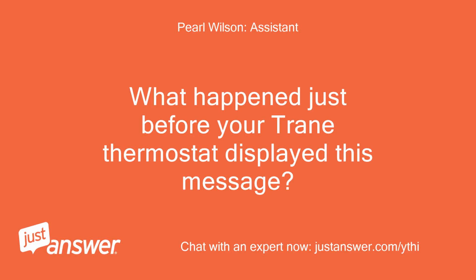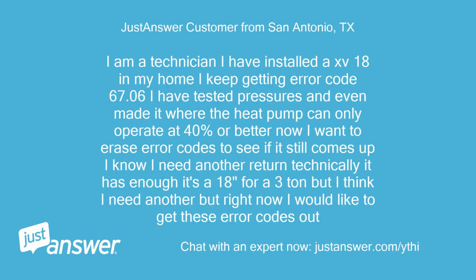I am a technician and have installed a unit in my home. I keep getting error code 67.06. I have tested pressures and even made it so the heat pump can only operate at 40% or better. Now I want to erase error codes to see if it still comes up. I know I need another return. Technically it has enough, it's at 18 inches for a 3-ton, but I think I need another. Right now though, I'd like to get these error codes out.